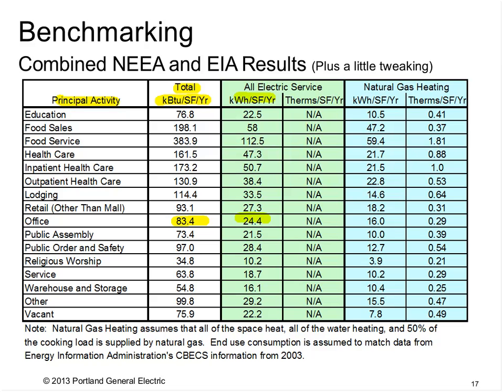Now, if you've got an office space that has gas for heating and gas for water heating, we would expect the electric energy consumption to drop and the therms consumption to come into play. So in that scenario, we would expect 16 kilowatt hours per square foot per year and 0.29 therms per square foot per year. That gives you a sense for the magnitude of therms.